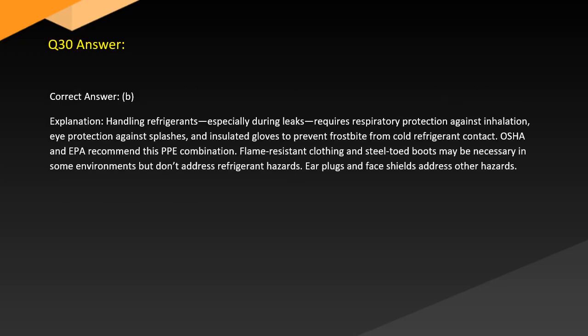Answer. Correct answer: B. Explanation. Handling refrigerants, especially during leaks, requires respiratory protection against inhalation, eye protection against splashes, and insulated gloves to prevent frostbite from cold refrigerant contact. OSHA and EPA recommend this PPE combination. Flame-resistant clothing and steel-toed boots may be necessary in some environments but don't address refrigerant hazards. Earplugs and face shields address other hazards.